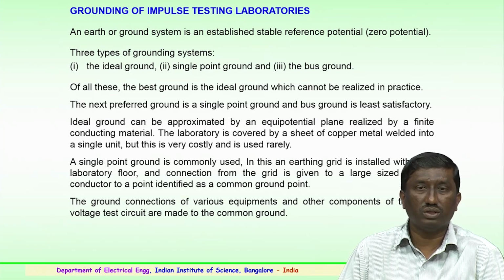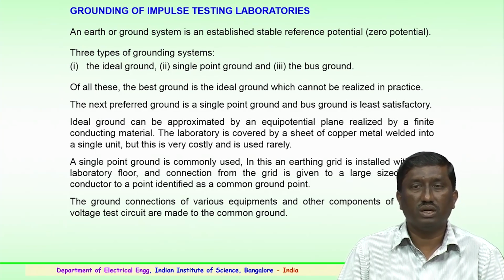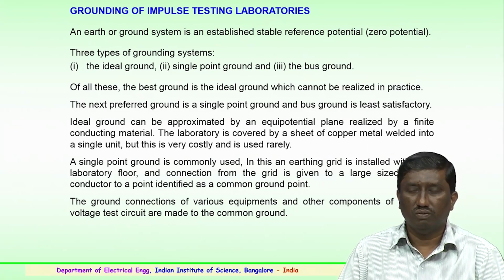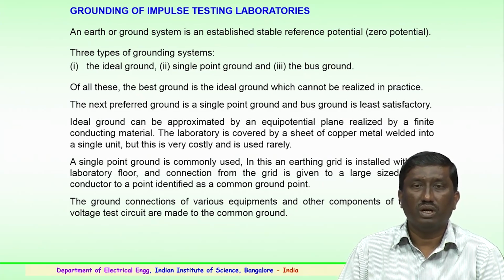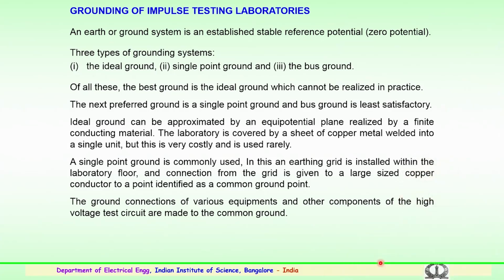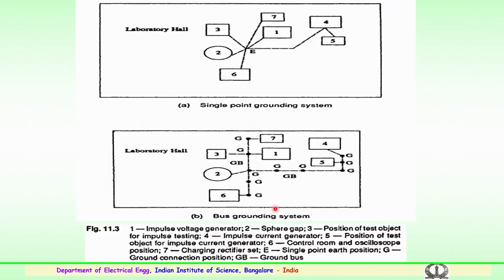So, a single point ground is commonly employed. In this, an earthing grid is installed within the laboratory floor, and a connection from the grid is given through a single large sized copper conductor to a point identified as a common ground point. So, it is very important. The ground connections of various equipments and other components of the high voltage test circuits are normally connected to this common ground. So, this gives the information about the single point grounding and also the bus grounding.